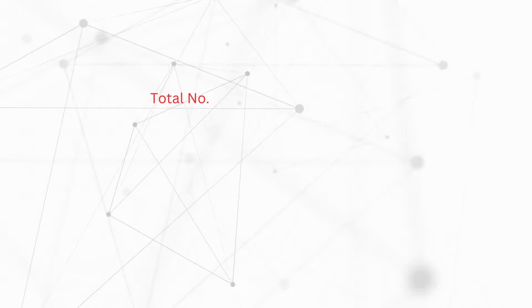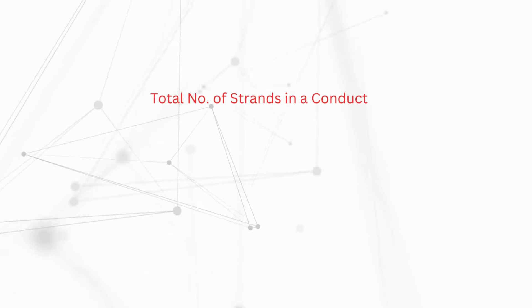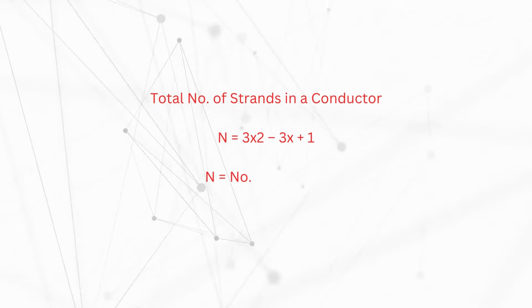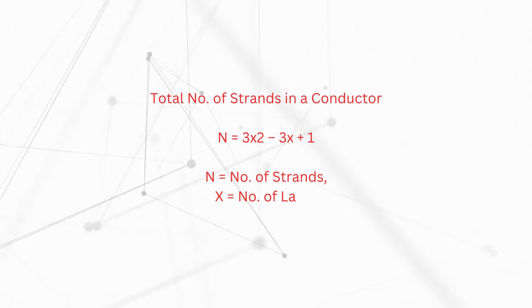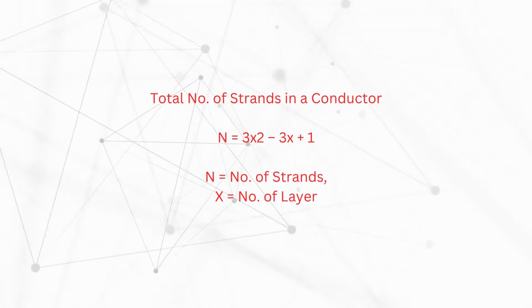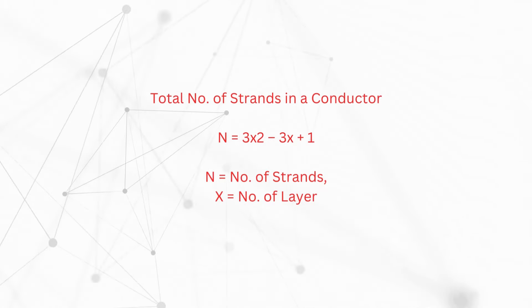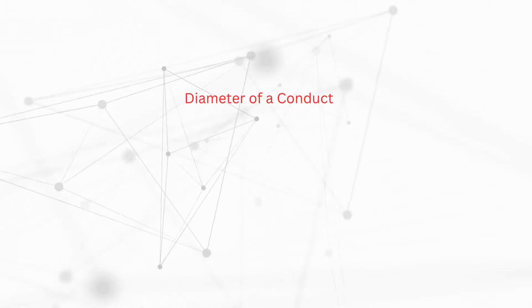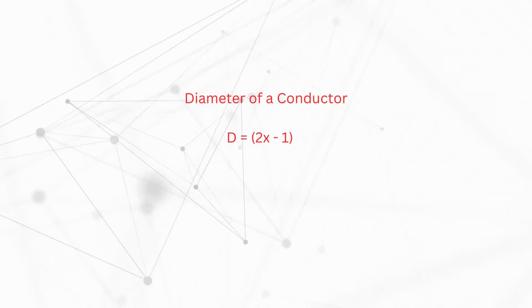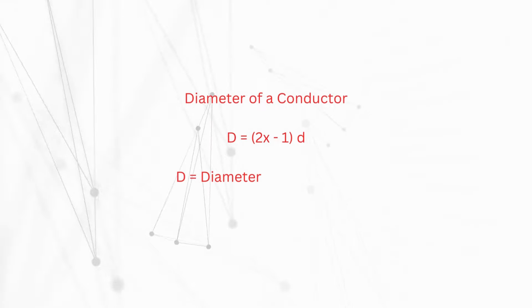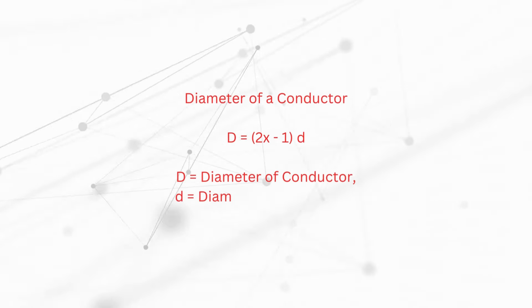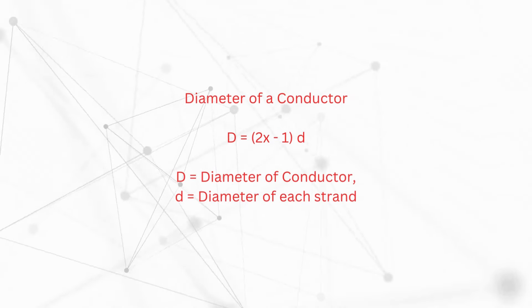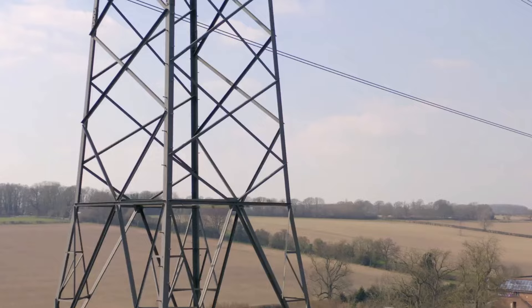The total number of strands in any conductor is determined by a specific formula: n = 3x² - 3x + 1, where n represents the total number of strands and x represents the number of layers in the stranded conductor. Similarly, the diameter of the conductor can be calculated using another formula: D = (2x - 1) × d, where D is the diameter of the conductor and d is the diameter of each strand.